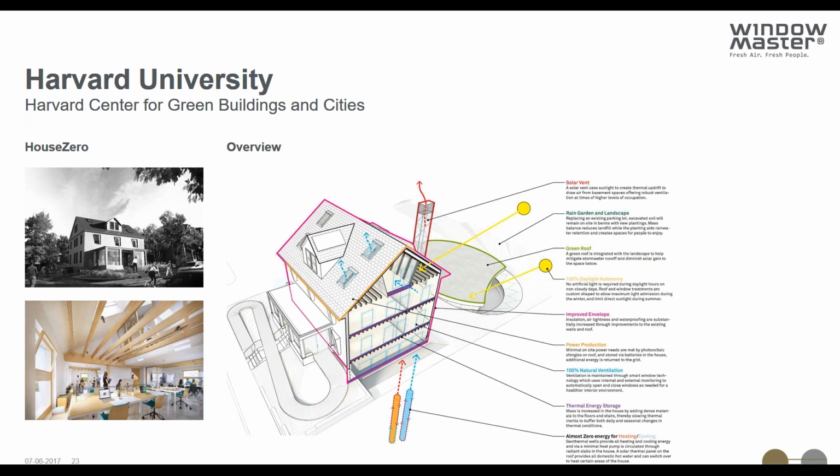But I can just briefly say that everything is natural ventilation, and we have also made this solar chimney, because there's a high basement here where we have facade windows, but it's a meeting room, and then we have made this solar chimney, which can increase the benefits of the natural ventilation, and also extend the season of how much we can use the natural ventilation for that space. Yeah, but again, we have actuators, motorized windows on our windows, and we have our own system. And of course, besides the motorized and natural ventilation, we also control the heating and cooling for this building, but also the solar shading. And for that, we also make some control strategies. So, for instance, when we open the window to a certain extent, we will do the interlink or interconnect with the heating and cooling system as well.